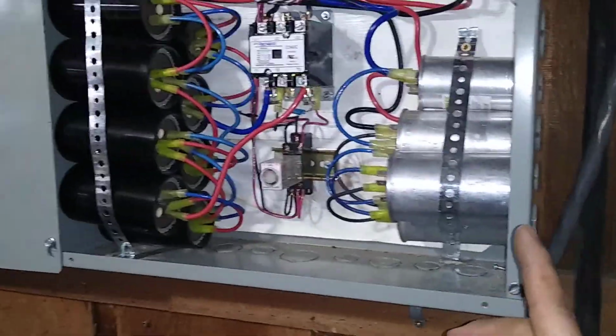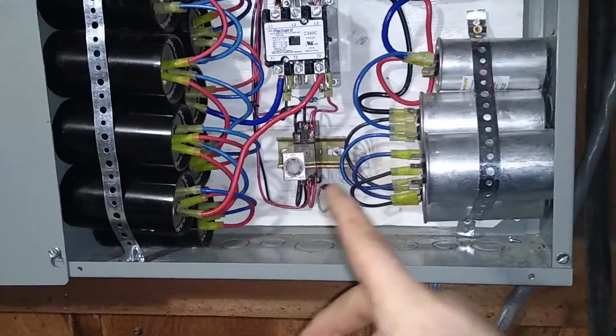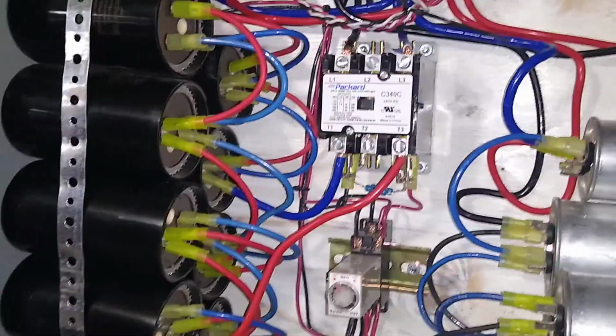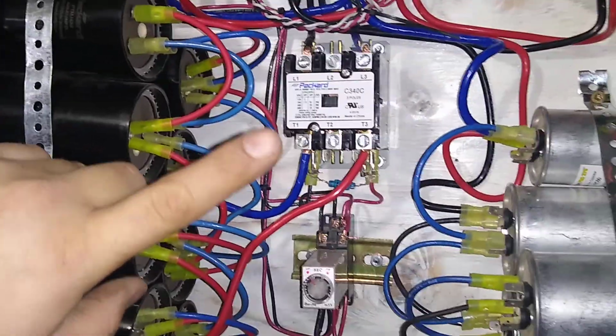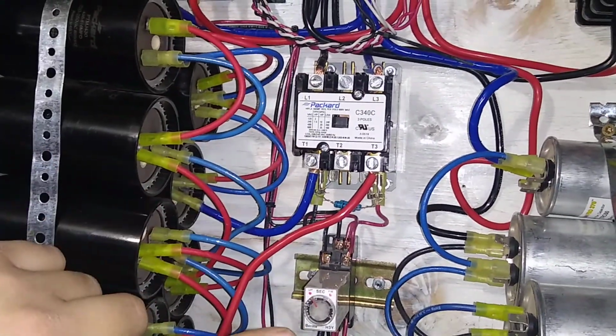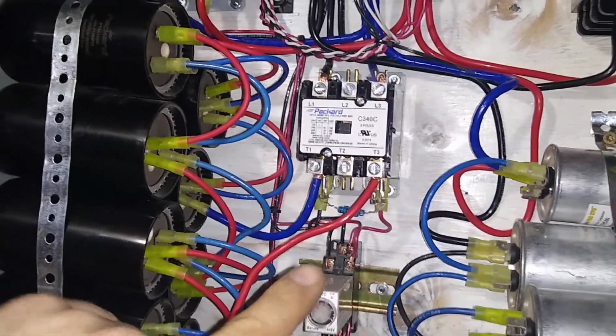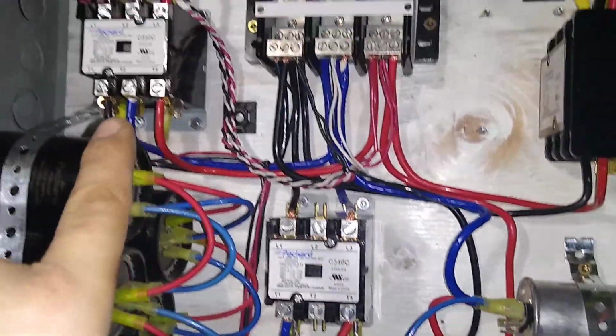E-stop, run button. Run capacitors, start capacitors. 0 to 1 second timer for the engage the start capacitors. Not only does it engage the start capacitors via this contactor, but then when it turns off, it's a double pole, double throw, and then it sends power up to this contactor, allowing the output of power.